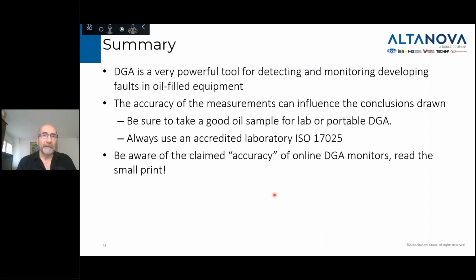So as a summary, DGA is a very powerful tool for detecting and monitoring developing faults in oil-filled equipment. And the accuracy absolutely influences the conclusion. The first thing, you have to make sure that you take a good oil sample for lab or portable. It's absolutely critical that people follow the IEC spec specifically on how to take a good oil sample in your transformer. If you're going to send it to a lab or if you're going to use a portable DGA, it tells you specifically how to flush. It tells you specifically what kind of container you should use to really minimize the loss of any gases.